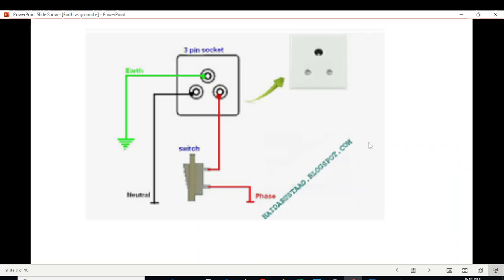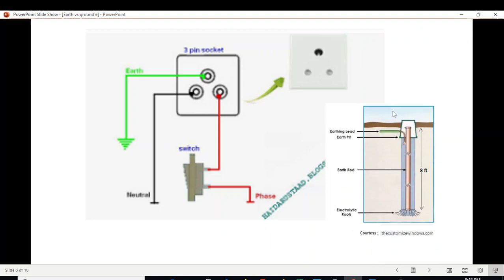Now, unfortunately, in our country, the earth point in the domestic wiring is non-existent. All that has been shown here, but it actually does not exist. If you look around your house, there is no point dug in the house for the earth point. So, for safety, we should dig this type of pit and connect all our equipment, or the body of the equipment, with this. Now, if this cannot be done for any reason, the simplest choice should be to connect a metal pipe to all the ground points in the house.